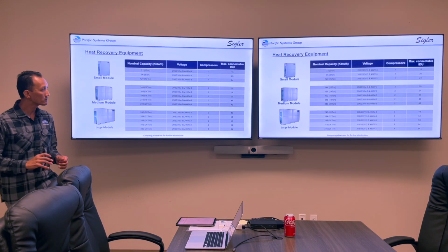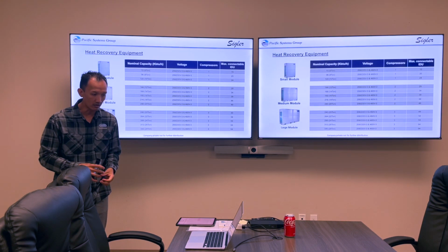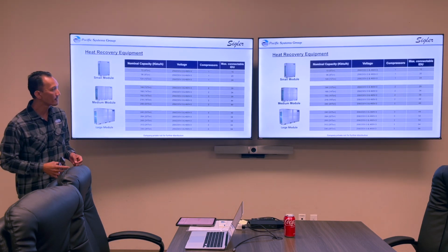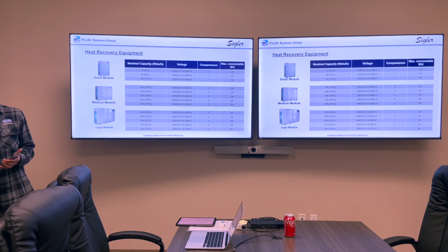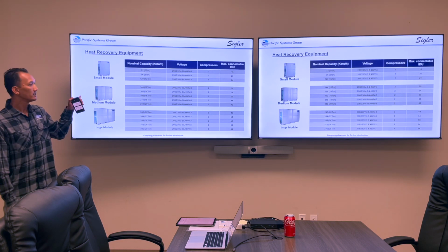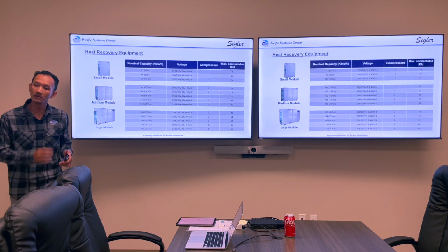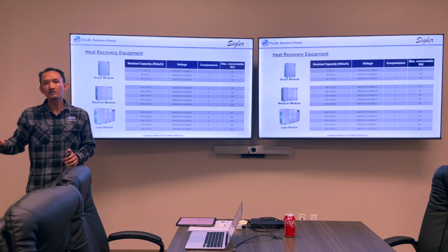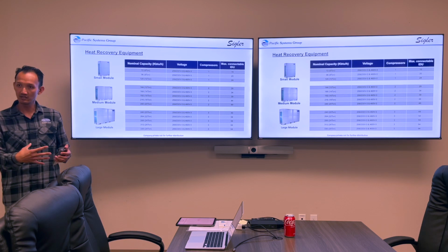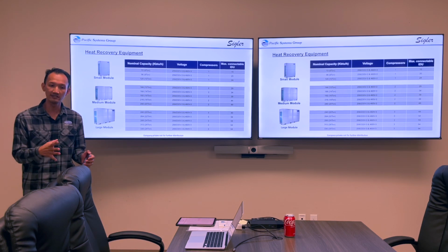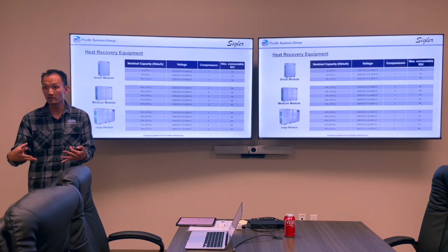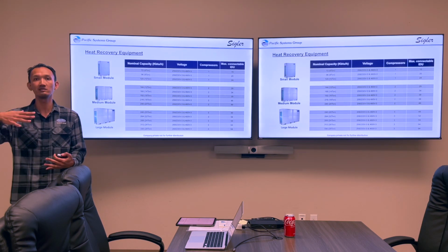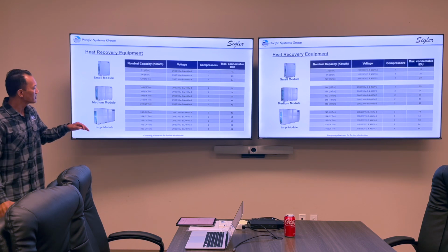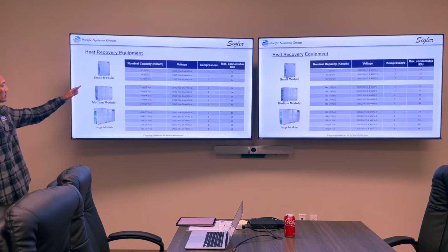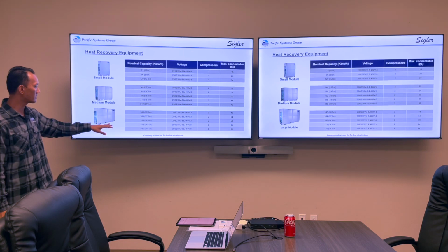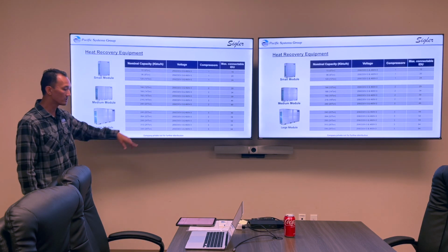And then one real quick thing I want to point out on our Carrier 2-pipe heat recovery system is our outdoor units. They're pretty unique in the industry. You'll see that they come in a small, medium, and large module. Pretty much everybody else, when you go to the higher tonnages, they take a 10, 12, or 16-ton condenser, and you pair them, or you get 3 of them and pair them together, and you get to your higher tonnages, right? On Carrier 2-pipe heat recovery, they come in small, medium, large modules. So for example, our large module goes from 20 all the way up to 28 ton.